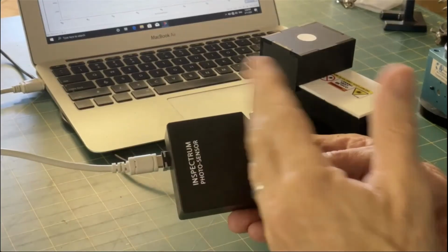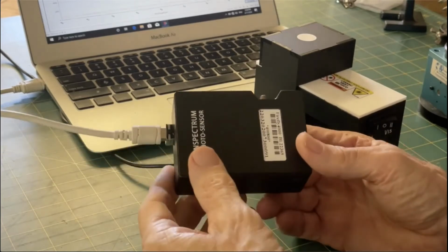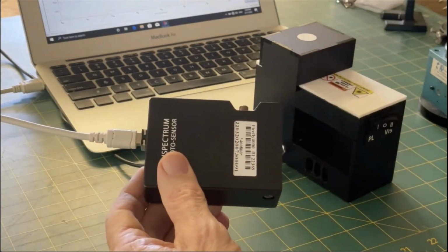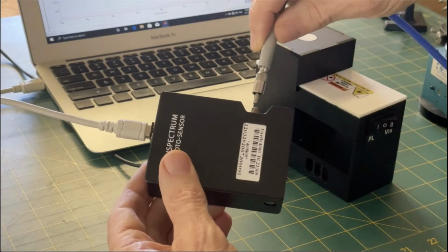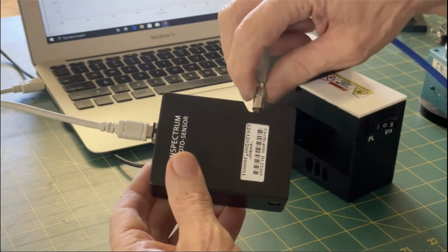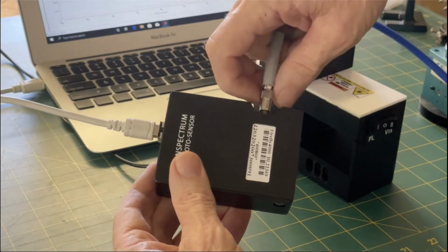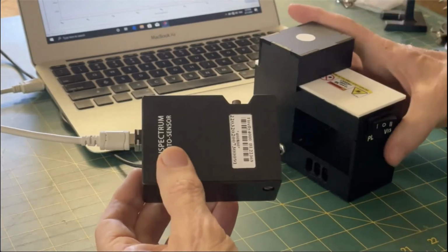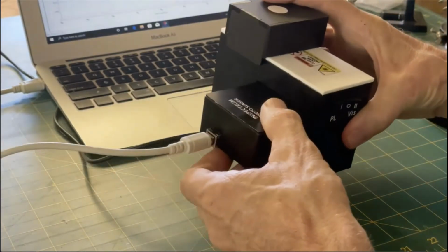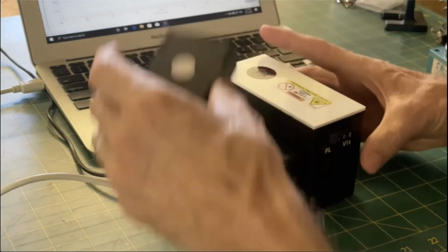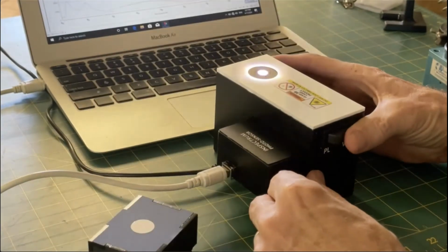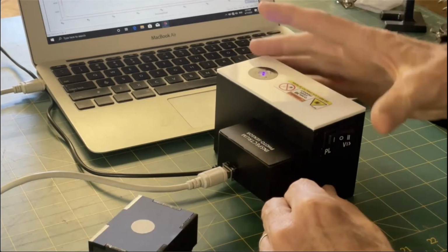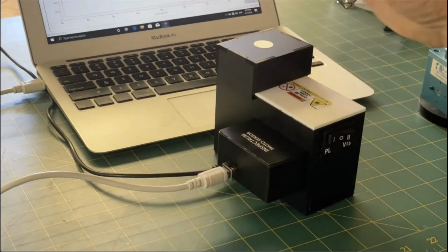These can come in bigger sizes for greater sensitivity, either in resolution or just simply sensitivity. And to get the light into it, it can either happen with the aid of an optical fiber, which some systems use for versatility, or in the instance of the InSpectrum, the light is focused directly onto the slit. And for the light, there are two modes. There's a white light, where a sample goes there, or a laser, a 405 laser, and a lid to go over.